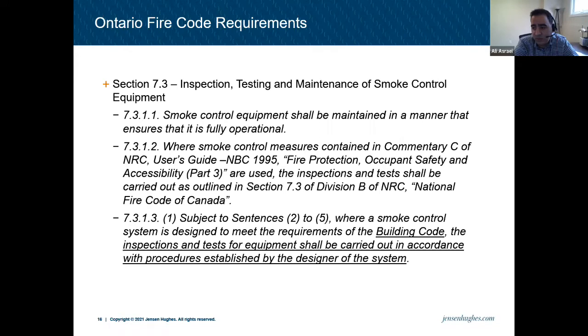This sentence is talking about a smoke control system, which could be a measure, but you can have a smoke control system which is not a measure, basically a 3.2.8 system that we talked about. It's not specifically for a high building. But then at that point, you need the designer, even if there is a measure that includes a smoke control system. Because to clarify a bit, when we're talking about measures, it's not only a smoke control system. Let's say measure N, vestibule, or measure A asks for certain vestibules with fire resistance rating to separate below-grade shafts from the floor area and stuff like that. So those are not technically a smoke control system. It is part of the measure, but it's not the smoke control system, right?